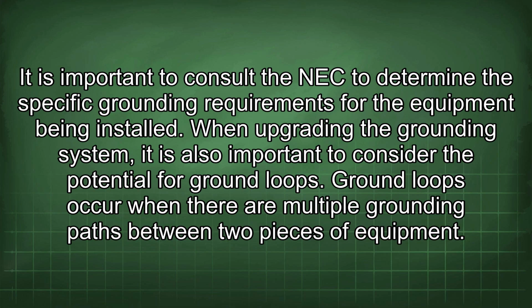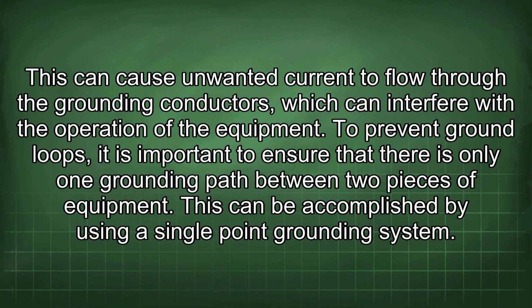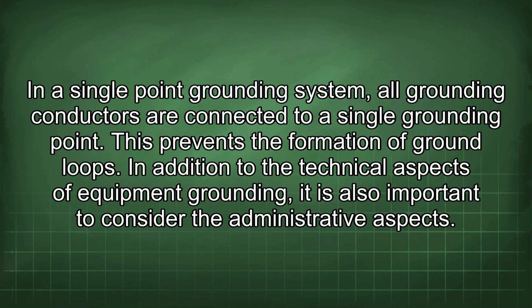When upgrading the grounding system, it is also important to consider the potential for ground loops. Ground loops occur when there are multiple grounding paths between two pieces of equipment. This can cause unwanted current to flow through the grounding conductors, which can interfere with the operation of the equipment. To prevent ground loops, it is important to ensure that there is only one grounding path between two pieces of equipment. This can be accomplished by using a single-point grounding system. In a single-point grounding system, all grounding conductors are connected to a single grounding point. This prevents the formation of ground loops.